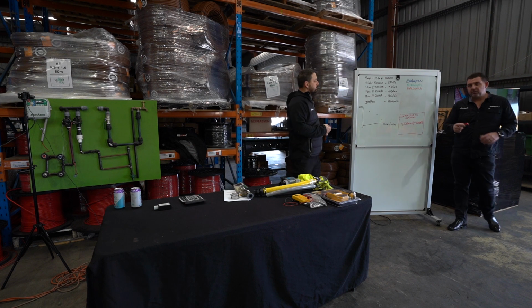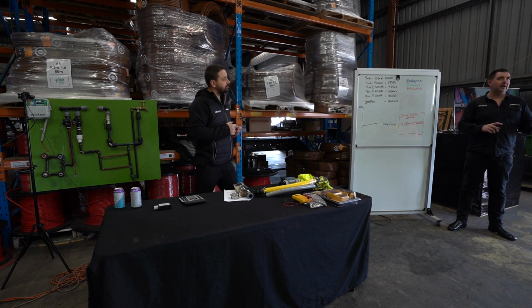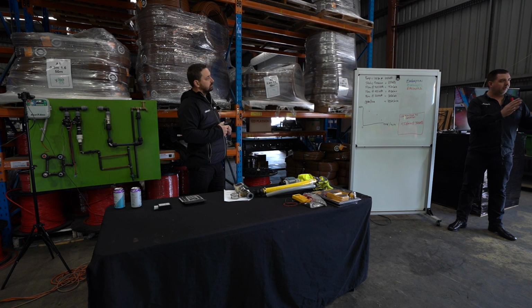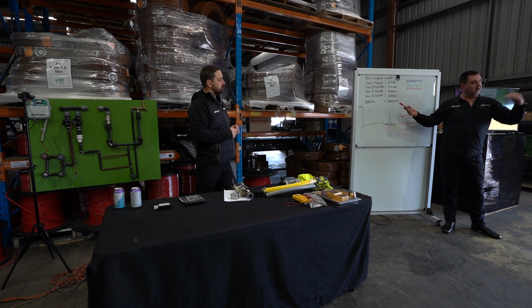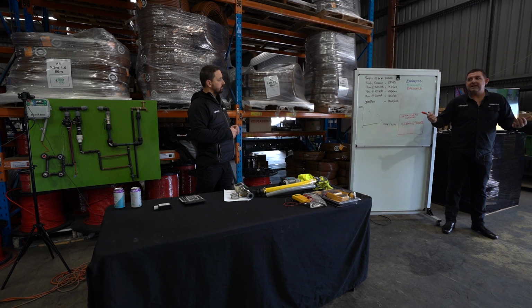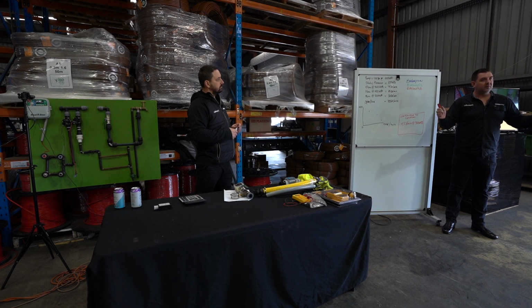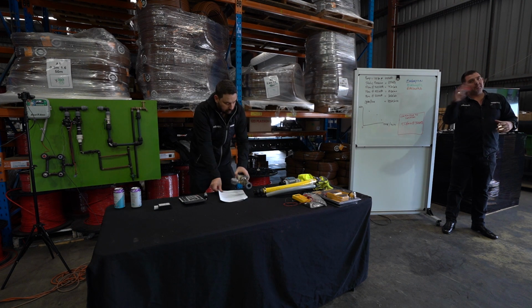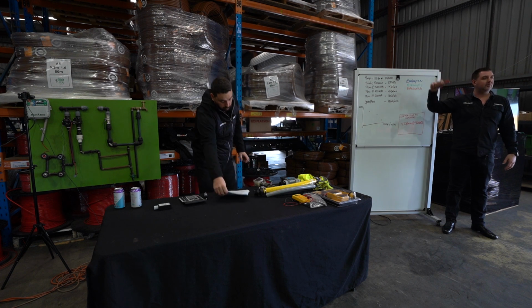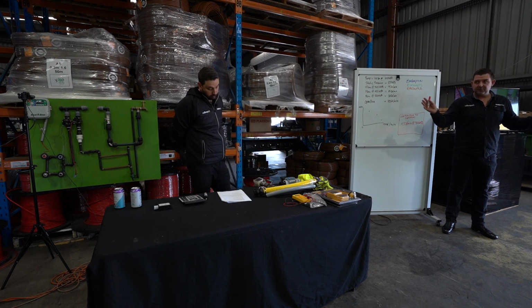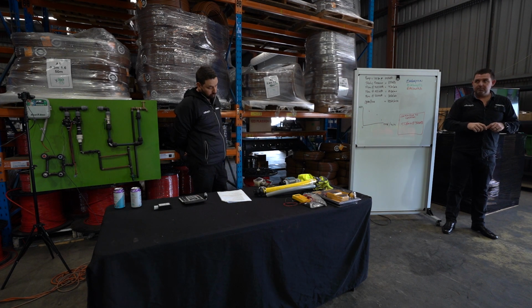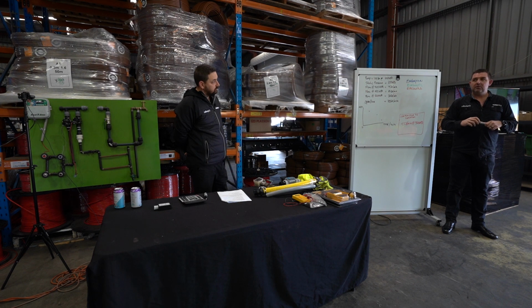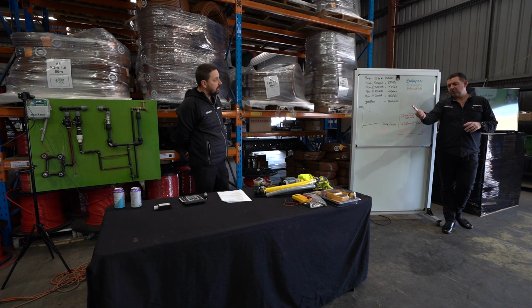There's not a lot of cases, but there's cases in Charles Sturt and other councils where they've got the flow, but they don't have the pressure. So they'd be getting, obviously you can see 100 litres a minute might be coming into a system, but it's at 80 kPa or something. What they'll do is put a tank that catches that water and then pump it back out at the same flow, but at a higher pressure. So the system can work 24/7 if it needed to, because all you're doing is increasing the pressure, but not the flow. But as you'll see in the document there, you can't decrease your pressure using flow control. That's a separate thing anyway.